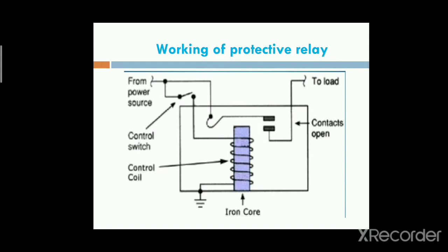All the relays employed for protection against short circuits operate by the currents and voltages supplied to them by the CTs and PTs. Failures in the system are indicated by individual or relative changes in the currents or voltages supplied to the protective relaying equipment.